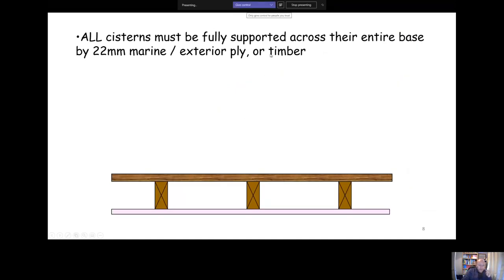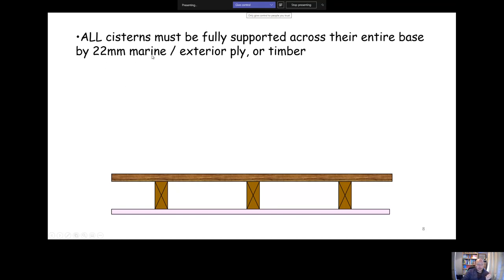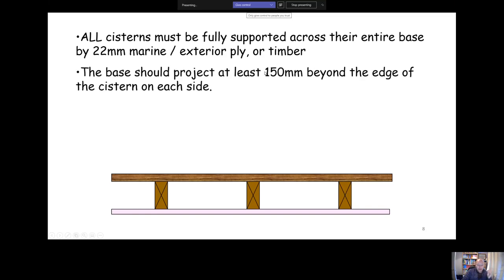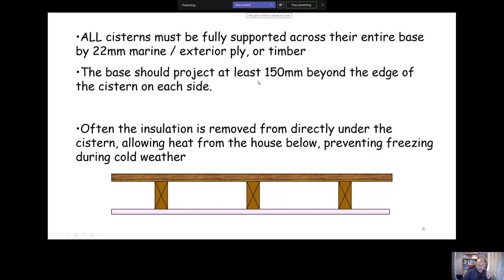All cisterns, and this is key, all cisterns must be fully supported across the entire base using something that's going to be resistant to water. That could be marine ply or timber, either is fine. It needs to be fully supported across the entire base plus an extra 150 mil on each side. Sometimes, this isn't a regulatory requirement, you might remove insulation from underneath the system. That's essentially to allow some of the heat from the house below to gently warm the system to prevent freezing during the winter.